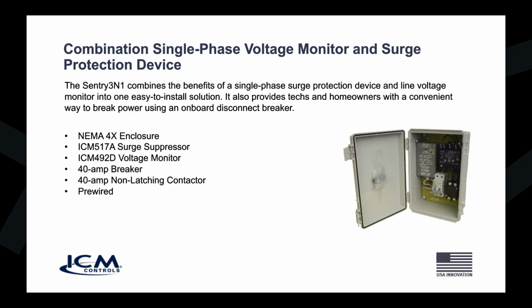You also got the brand new ICM 492D with its upgraded advanced features for voltage monitoring, so you can monitor your voltage sags and your rises in the voltage. So you got the benefit of the 517A surge, the benefit of the 492 voltage monitor, plus a nice non-latching contactor to break inductive loads like motors and compressors. A lot of your competitors' models use block relays, and block relays are not really good for inductive loads. Inductive loads are big motors and compressors, things like that. When we disconnect you, we fully disconnect you. And some of those latching block relays could fail and latch in the latched position, leaving you still connected, which is kind of a bad thing if you're trying to protect against surges and voltage issues.